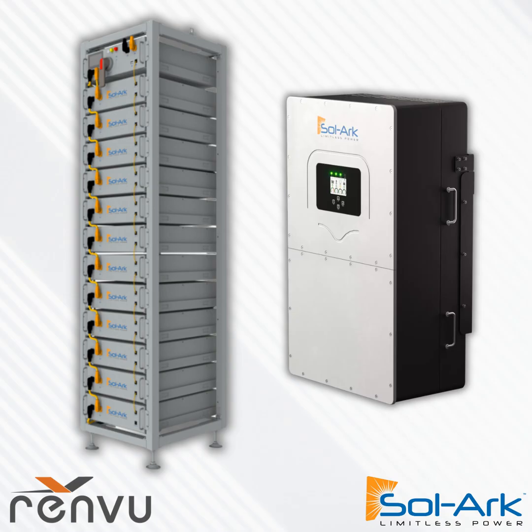Best resources for controls such as peak shaving functions: we have a peak shaving target based on seasonal control, which is best programmed on site. That's probably a gotcha with our formatting, since you have to set the seasons on site. This gives you 3-season control, and a 3-season set point for peak shaving. You'd program the inverter to charge the battery up to 100%, so that when usage is above the target it discharges the battery, and when under the target it charges the battery.